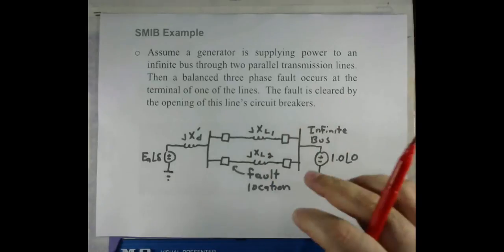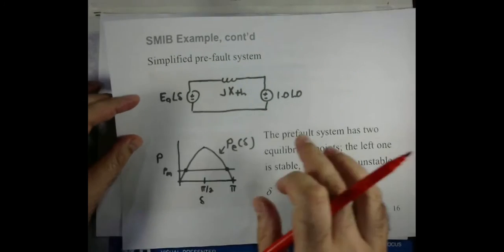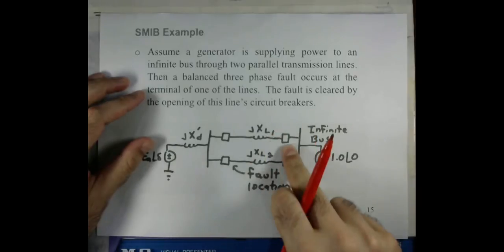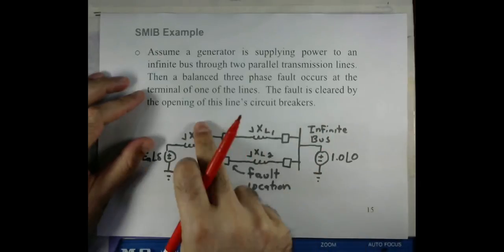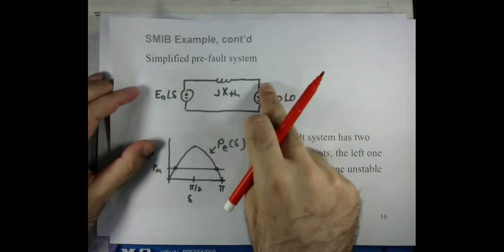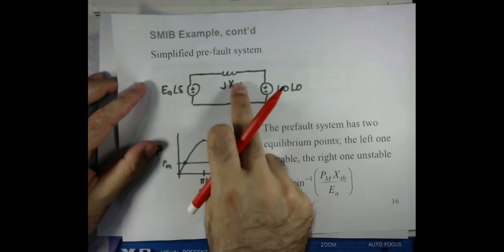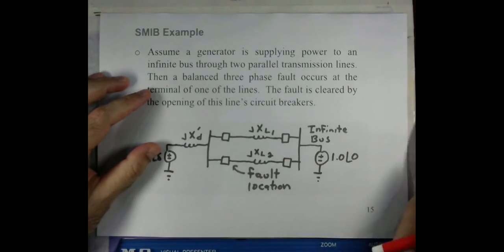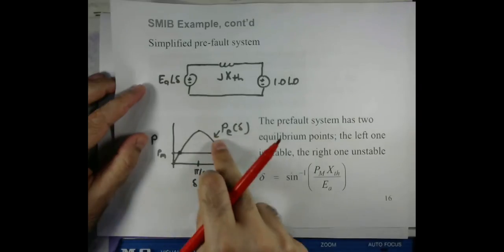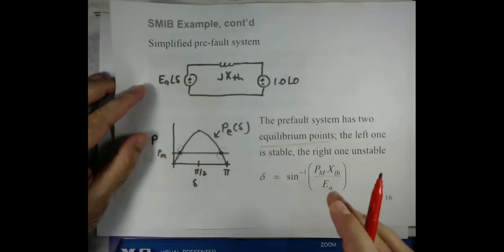For the pre-fault analysis, since the two transmission lines are in parallel, we find their equivalent inductive reactance using the parallel combination formula. Adding the equivalent transmission line reactance to the generator transient reactance X'd gives the total reactance X_th. This gives us the simplified pre-fault system: the generator connected to the infinite bus through X_th. The pre-fault system has two equilibrium points on the power-angle curve.